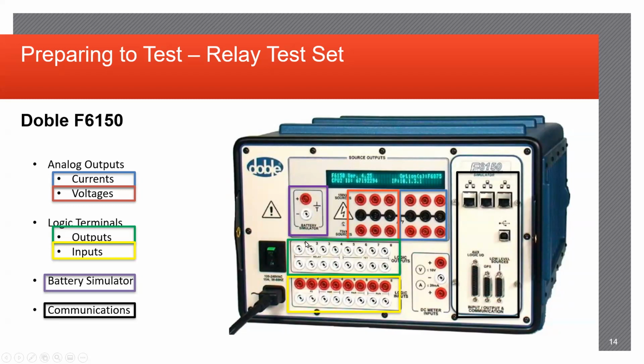This DC source will be plugged into your logic outputs if need be, which are usually normally open contacts when applied to DC voltage source on the top side. You'll connect the bottom side to any inputs going into the relay, and then you'll have your return back to the negative side. So this will stay open until you construct a test for this to close when needed and verify operation on the relay pickup.